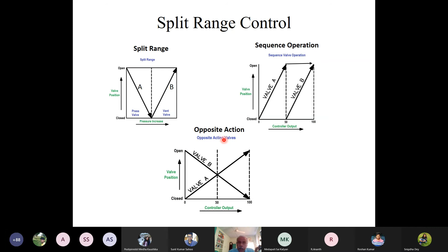And in the opposite action, the valve actions are in opposite directions. When the controller output is 0, one of the valves is fully open and the other is fully closed, and as the controller output increases, the fully open valve is closing and the fully closed valve is opening. At 100% output, valve A becomes fully closed and valve B becomes fully open. So this is basically the opposite action valve operation. Split range control basically depends on how the valves, or the manipulated variables, operate based on the controller output signal.